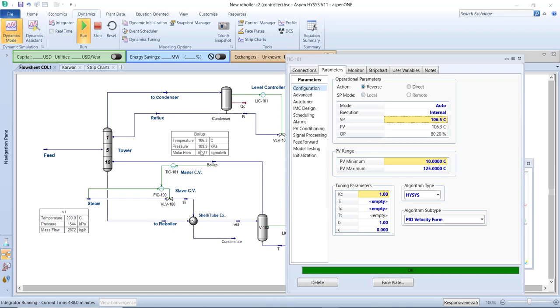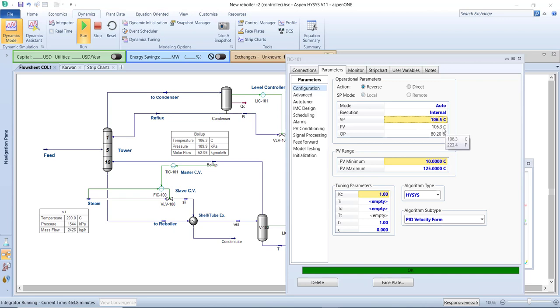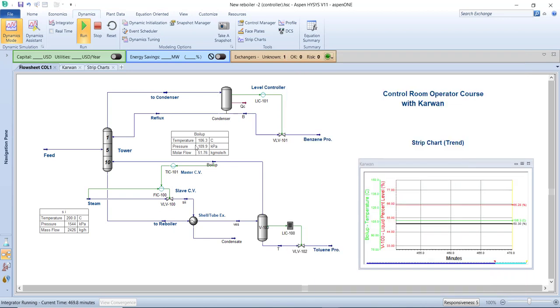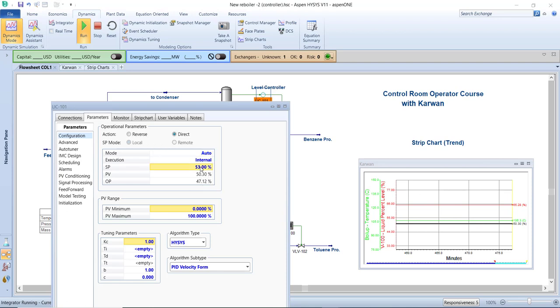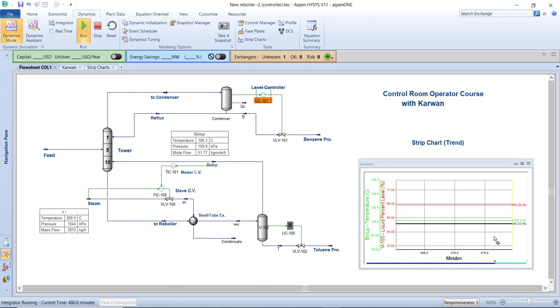For example, suppose we take a sample from the bottom of the tower and the composition shows light hydrocarbons coming down. The supervisor asks you to increase the setpoint from 106.3°C to 106.5°C. Now look at the process response — the TIC is connected to the FIC, which controls the steam flow going to the shell-and-tube heat exchanger. It takes some time for the action to occur. I've rearranged the simulation: our new setpoint is 106.5°C but the PV is still 106.3°C — we need to wait for it to respond.